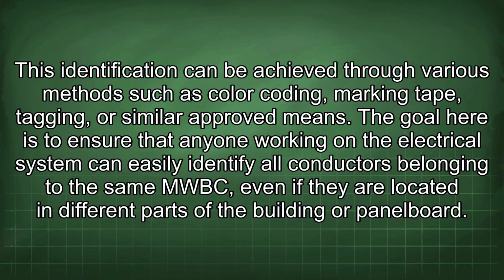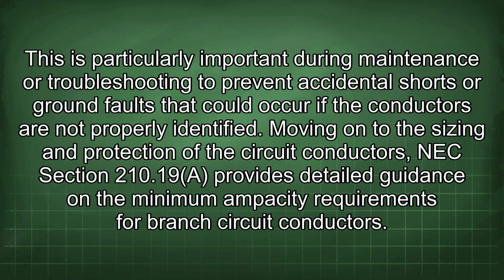similar approved means. The goal here is to ensure that anyone working on the electrical system can easily identify all conductors belonging to the same MWBC, even if they are located in different parts of the building or panel board. This is particularly important during maintenance or troubleshooting to prevent accidental shorts or ground faults that could occur if the conductors are not properly identified.